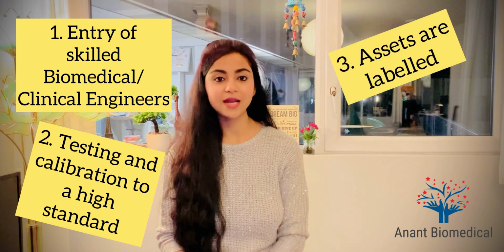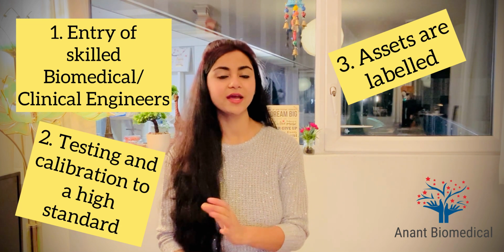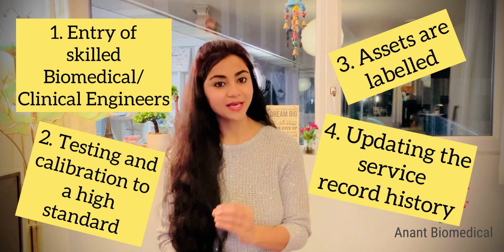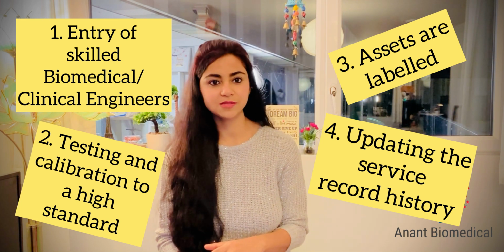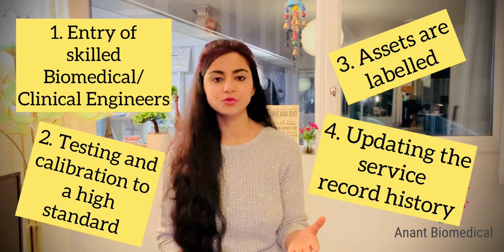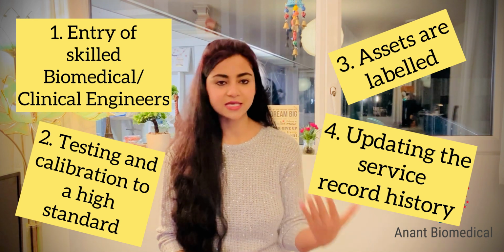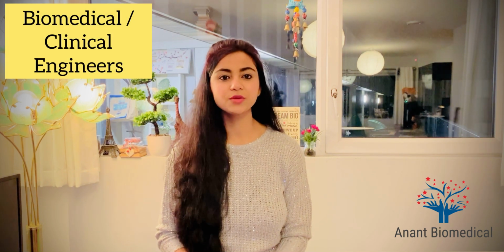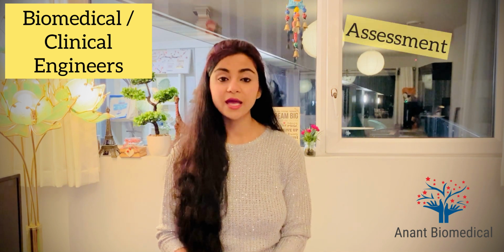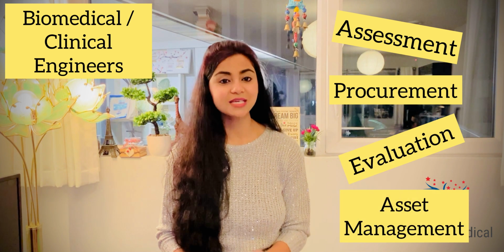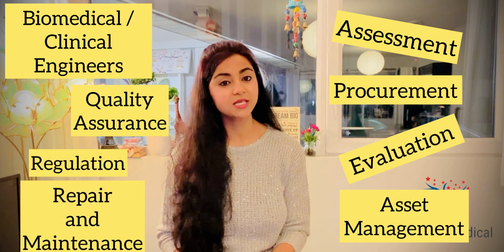Then asset labels are added to these products in order to build an electronic asset file or register. And lastly, the stickers are placed on these medical devices. So either a pass or a fail sticker is placed to make sure that the service record history is up to date. So this is what ideally should happen in the testing and calibration process of the medical device. By now you must have understood that biomedical engineers or clinical engineers remain at the core of maintenance of healthcare technologies, involving assessment, procurement, evaluation, asset management, quality assurance, regulation, repair, maintenance, and many other tasks related to medical devices. I would also like to bring to your notice that technological advancements such as prosthetics or surgical robots are the result of choral teamwork involving clinical engineers as the core professionals.